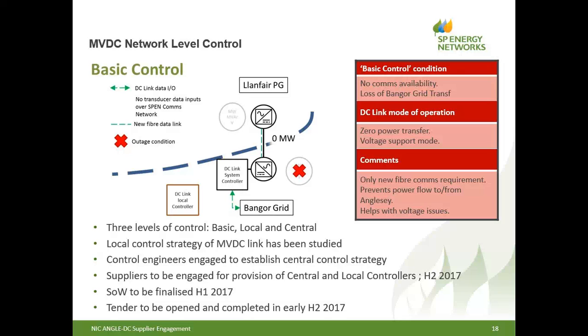So we are putting together a specification for a controller that we're going to go out to tender for later in this year. Our plan is to have it finished by about June, and we go out early in the second half of 2017 to see who can offer us what in terms of the control system. The basic control is really all about if we lose all the comms to the link, and also the worst case scenario for us, which is if we lose the Bangor transformer, the grid transformer at Bangor.